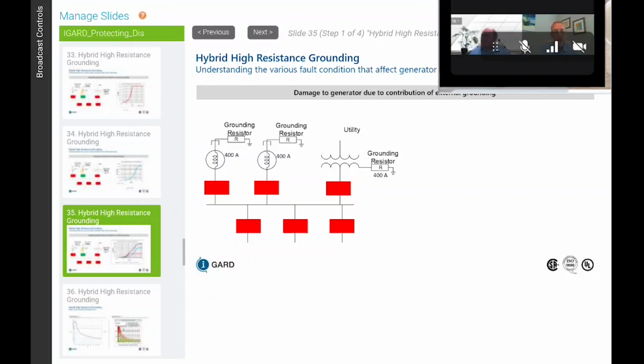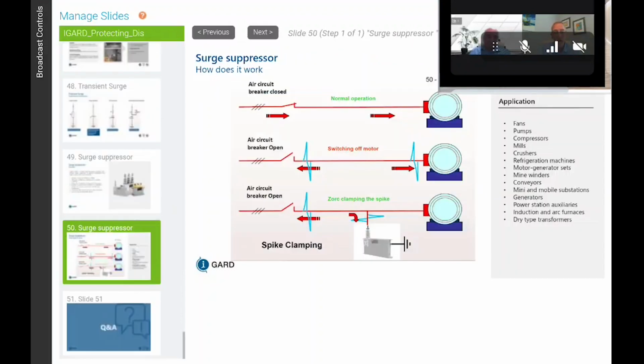Based on the surge protection image that you had on one of the slides, Jacob's interested, are you stating that we should add surge protection at the motor to protect the motor installation? Typically, he says, I see surge protection installed at the distribution equipment, not at the load. Yeah, we can put it at the load as well. If you don't have access to the source, you have to put it on the load. With this particular surge suppressor, we put it at the load because we had access to it there, and we would minimize the reflection point and protect the transformer and the motor as well.